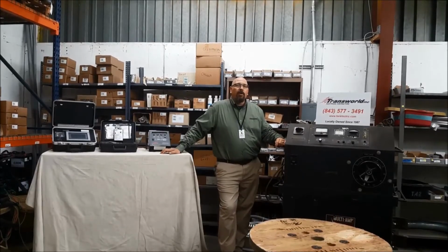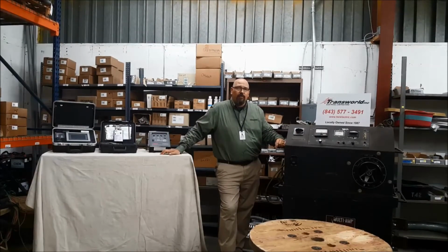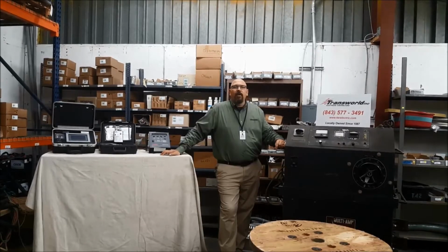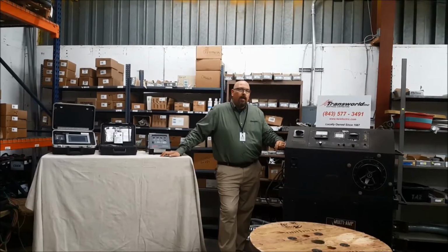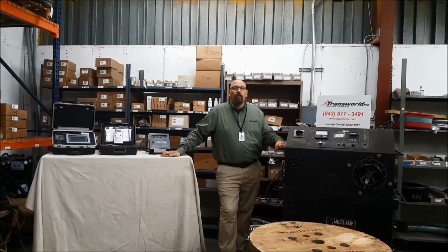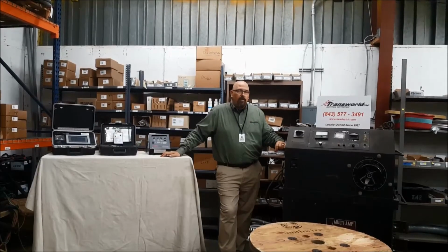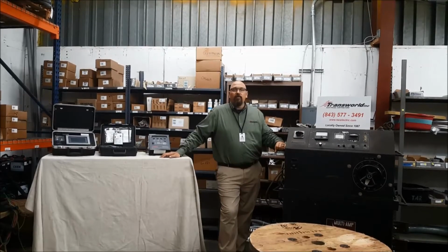Why do we use primary or secondary injection tests? One of the reasons is to protect personnel. If a breaker does not trip within its calculated trip time, it could cause a larger arc flash and could damage or hurt personnel. The other reason is to protect equipment. If a breaker does not trip within its calculated time, equipment downstream could be damaged more than expected.